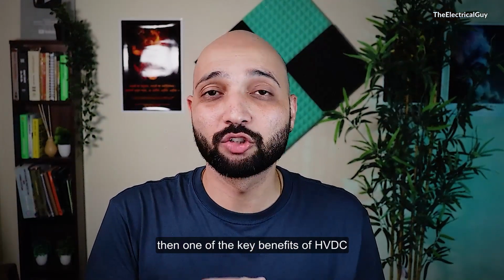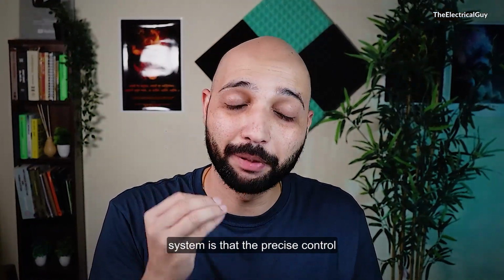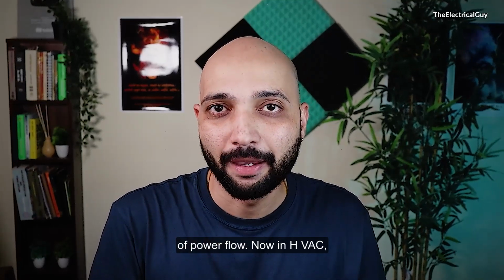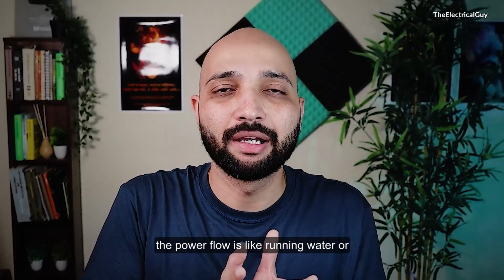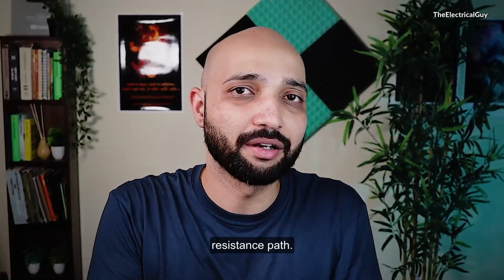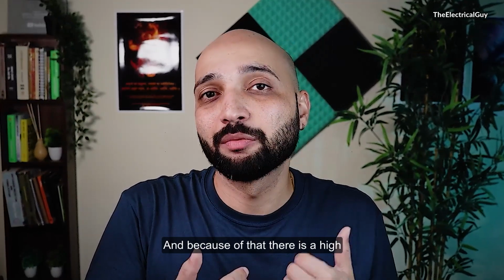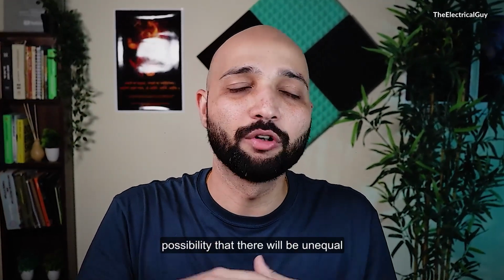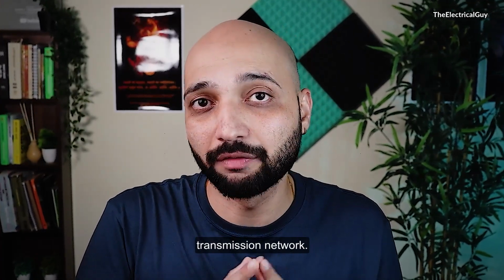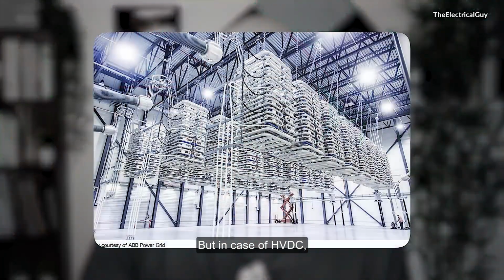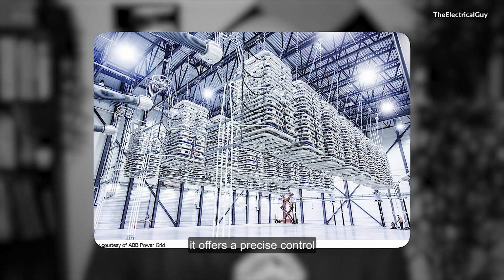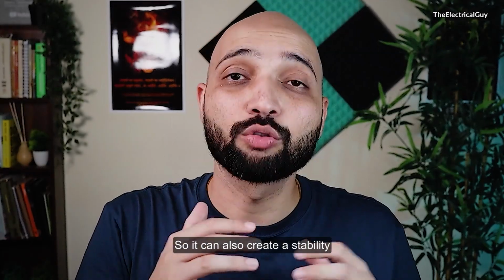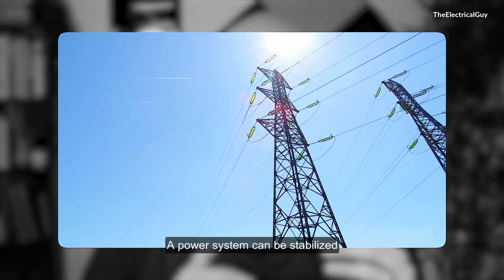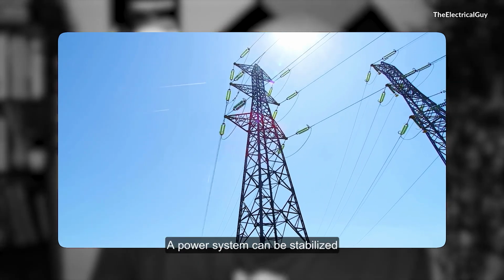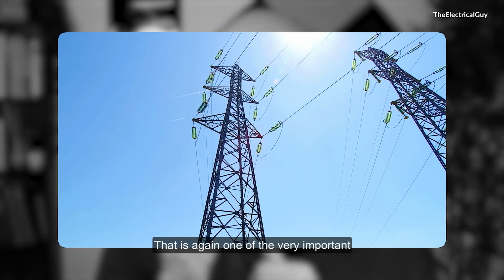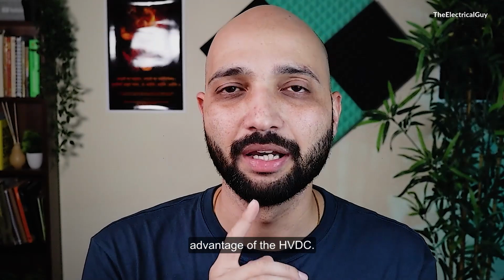Another key benefit of the HVDC system is precise control of power flow. In HVAC, the power flow is like running water, it will choose the least resistance path, and because of that there is a high possibility of unequal power distribution across the transmission network. But in case of HVDC, it offers precise control over the power flow, so it can also create stability in the system. A power system can be stabilized with HVDC. That is again one of the very important advantages of HVDC.